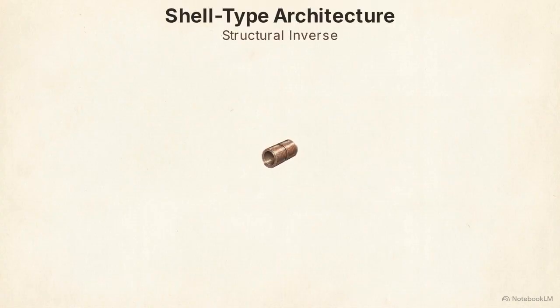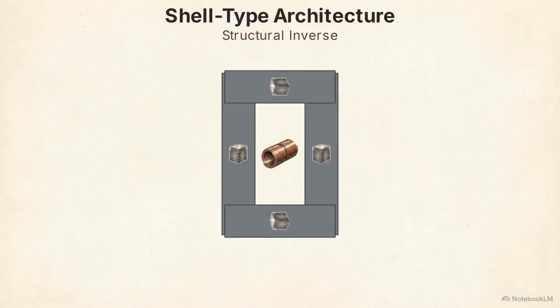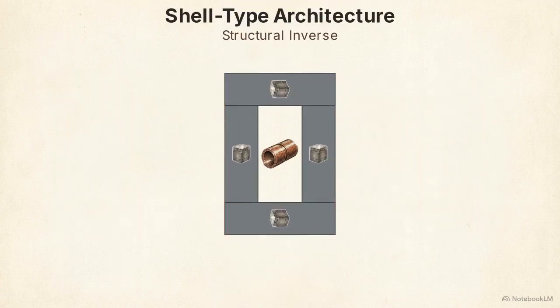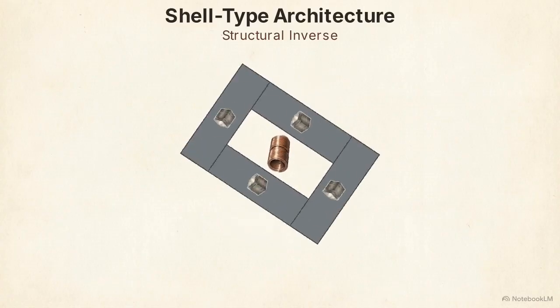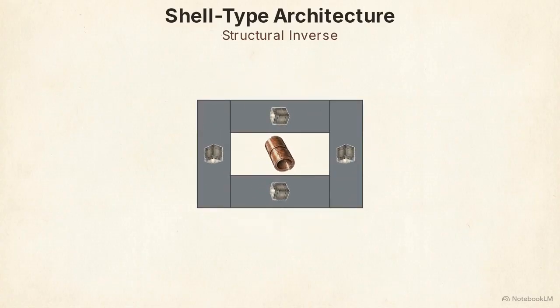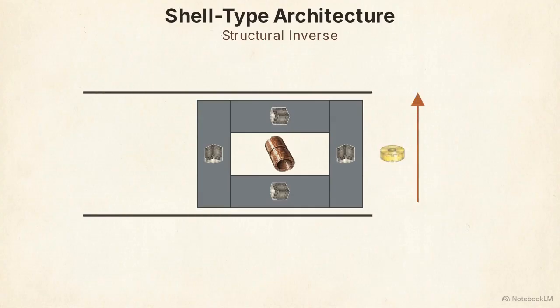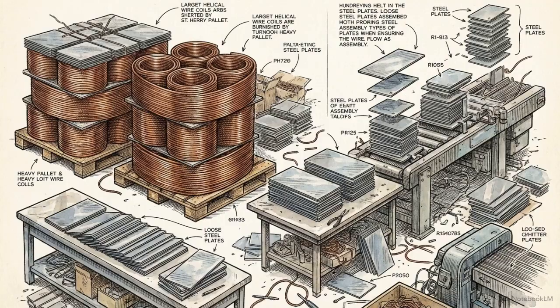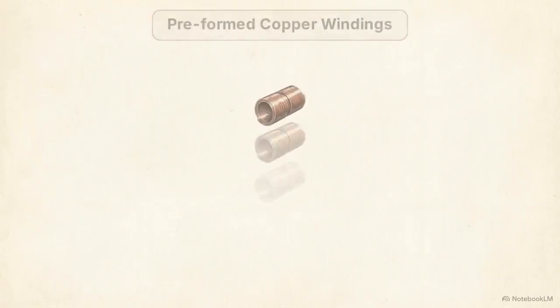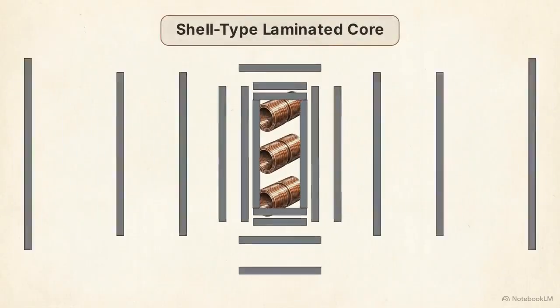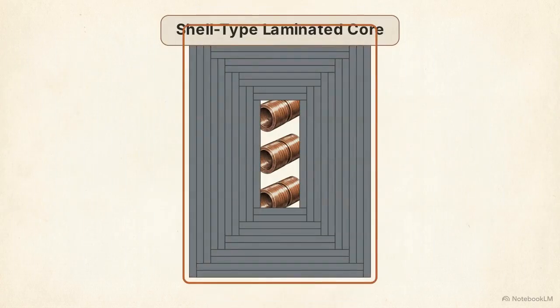However, severe spatial constraints in certain industrial applications require the alternative architectural solution, the shell-type transformer. This is the structural inverse of the core type. Here, the metallic core encloses the copper windings, physically shielding them from the outside. By encasing the windings, this architecture allows for either a vertical or a horizontal axis orientation, accommodating tight clearance constraints. Building it requires a complex assembly process. The factory must pre-form the heavy copper coils and then intricately build the steel core around them, piece by piece.